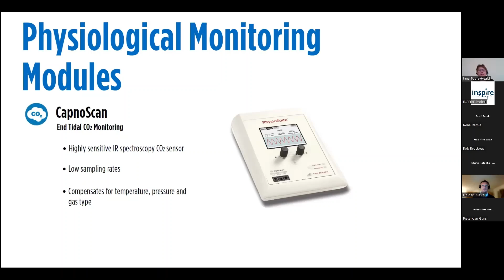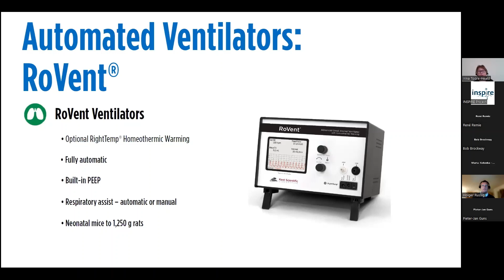This is our Rovent automatic ventilator that can be used as a standalone unit with either SomnoSuite or SomnoFlo or the traditional vaporizer. It has a couple of options. There's a Rovent Junior and then the Rovent Advanced unit that allows additional options like inspiratory and expiratory hold, and a built-in PEEP option. All you need to do here is just set the animal weight, and the unit will adjust all the other parameters.